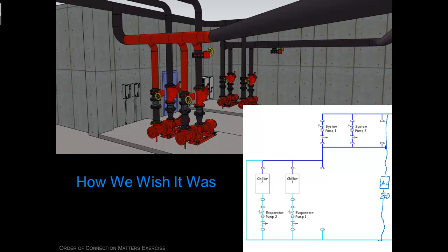And let's go ahead and look at this plant at that 750 GPM, 3/4 load condition. So there's 750 GPM of flow. We come back to the plant and we get to that first T. Now remember, we're at more than one machine's load, so we've got two chillers running.